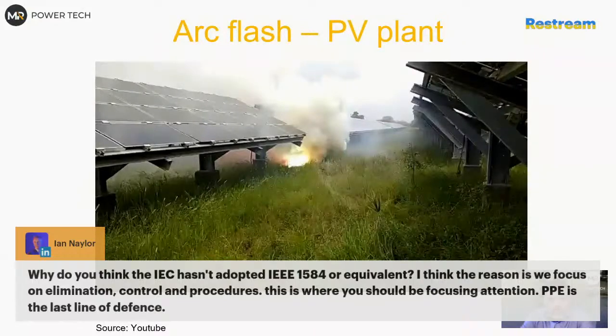So the problem is, as far as I see, I don't know why IEC still doesn't want to catch up on IEEE 1584. For me, the best idea would be to adopt IEEE 1584, not even NFPA 70E, just IEEE 1584, because that's actually what we are doing. It's allowed in a lot of local regulations that we can follow this when we talk about arc flash, because there's really nothing else.